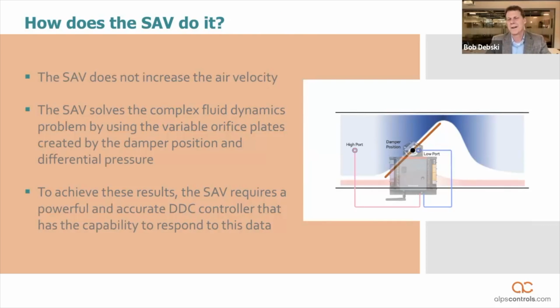So how does the smart air valve do it? Well, first of all, it does not do it by increasing the air velocity through the sensor. It doesn't do it with any type of new geometry, and it doesn't do it by any new type of exotic airflow sensor. It does it with all the same components you're familiar with: pitot tubes, flat blade dampers, and high accuracy differential pressure sensors. It looks very similar to what you're accustomed to.